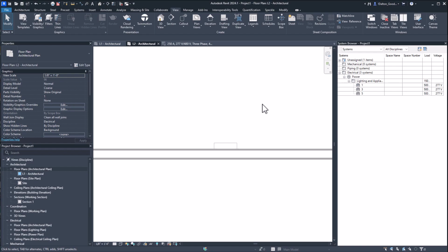So I just wanted to point that out because it gave me a bit of a headache just trying to figure out what was going on. It wasn't until somebody showed me that just deleting the panel caused the spares to become unnamed and just orphaned and not assigned to anything.